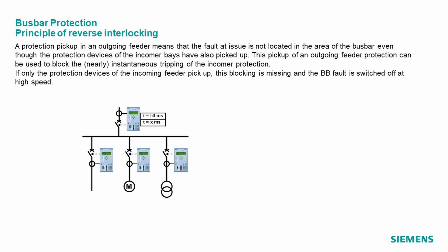If it is a very complex multiple busbar structure with longitudinal and cross-couplings, or if you are not satisfied with the release times of a reverse interlocking, then you have to use a specially designed busbar protection. From the SIPROTEC 5 portfolio, the 7SS-85 would then be used.